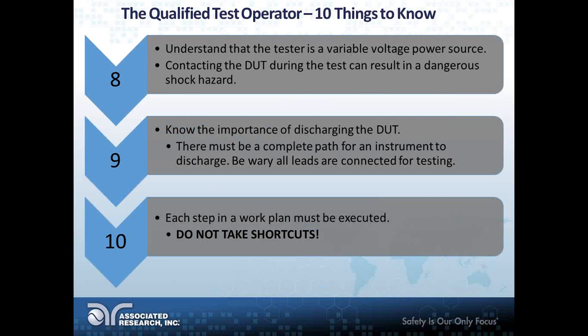If you know that your product, when you high pot test it, gives you about 3 milliamps of leakage current, go ahead and set your low limit to, let's just say, 1 milliamp. So if it goes below 1 milliamp, the test fails, letting you know, hey, I just got a low limit failure. Maybe my leads aren't attached properly. That has saved a lot of headaches on a lot of customer sites that I've seen, setting such low limits.